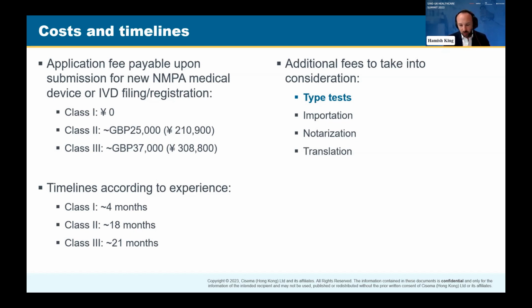There are many other costs, including local testing, which I mentioned, which is mandatory for class 2 and 3 medical devices. Your IVD products will also need clinical tests in China. There are other costs relating to notarization and the clinical evaluation report preparation, because you cannot simply translate your CE or UK CER into Chinese and submit it, because China has specific standards and requirements. There's translation, and other costs as well. Timelines I mentioned a little bit earlier: 4 months for class 1, 18 months for class 2, and approximately 21 months for a class 3 medical device. IVDs can be equivalent, but generally a bit more because they require clinical tests or more substantial trials on the whole for the China marketing approval application.